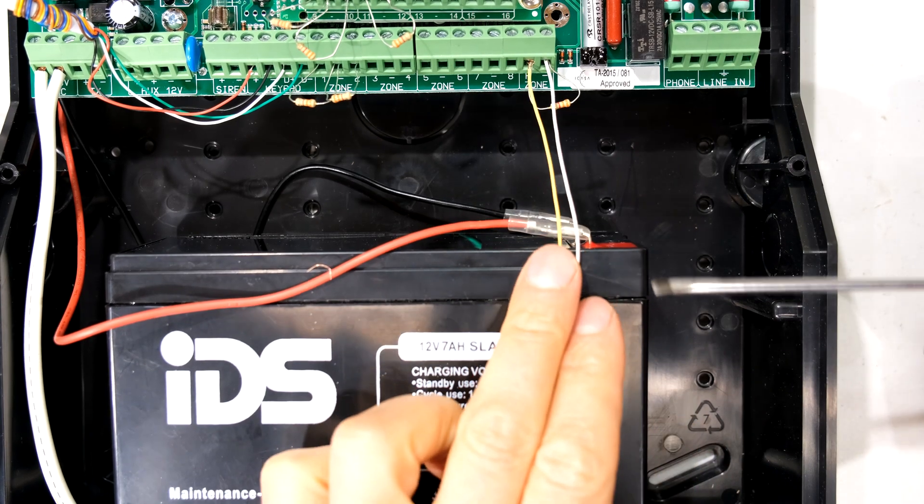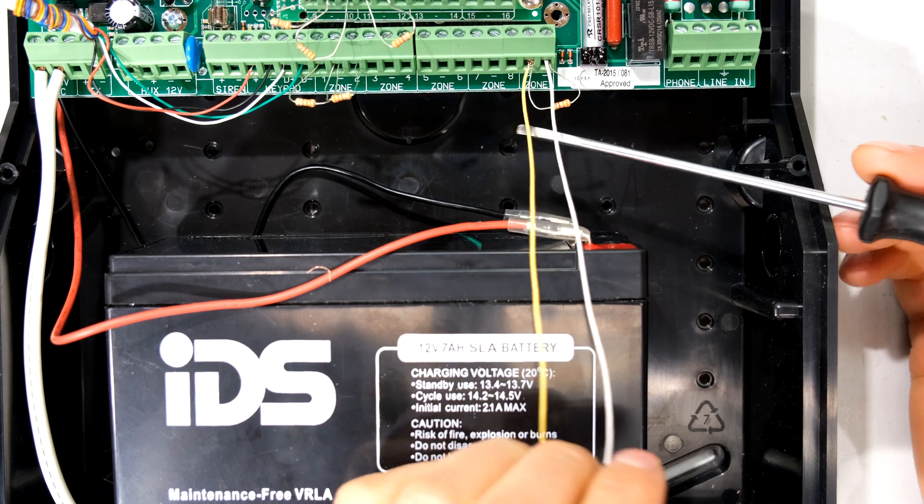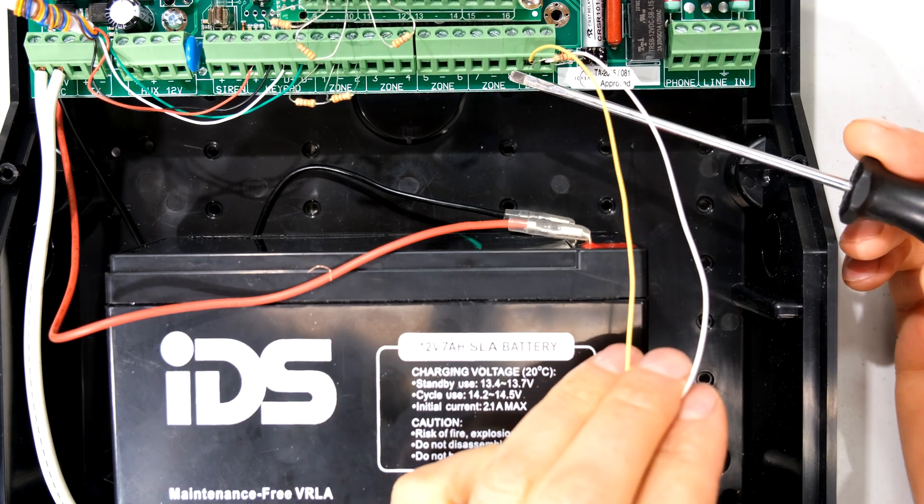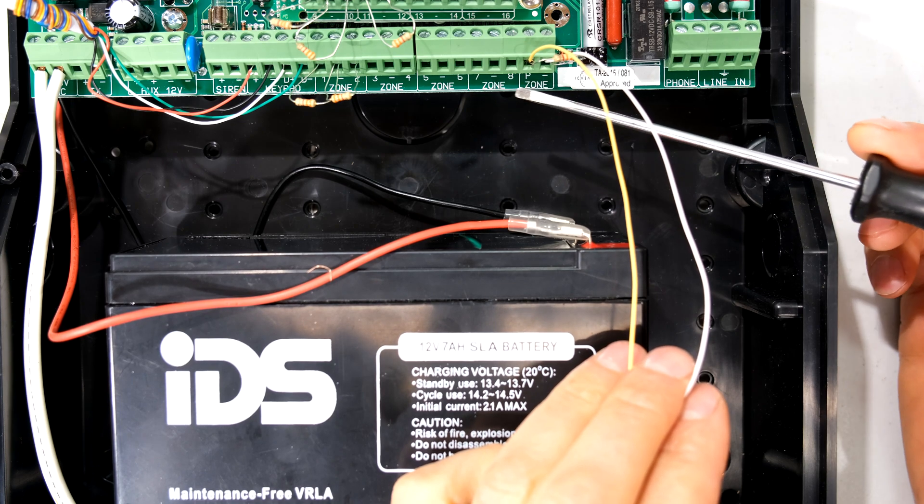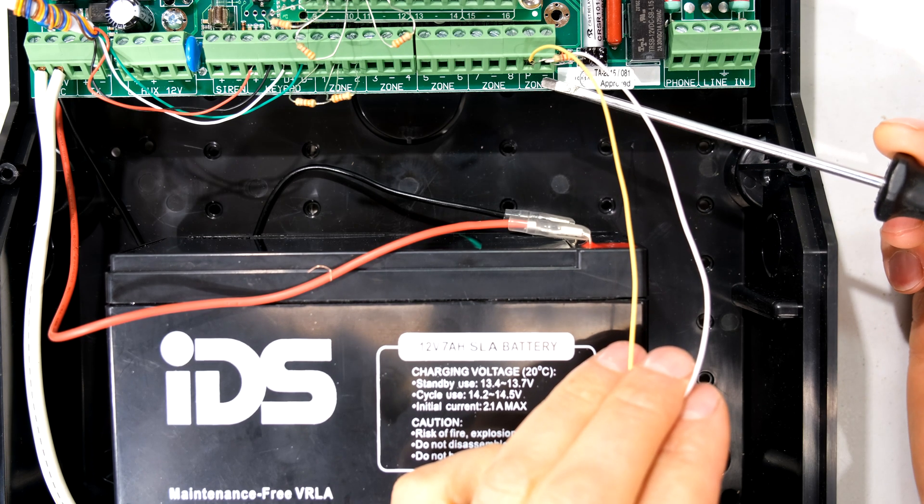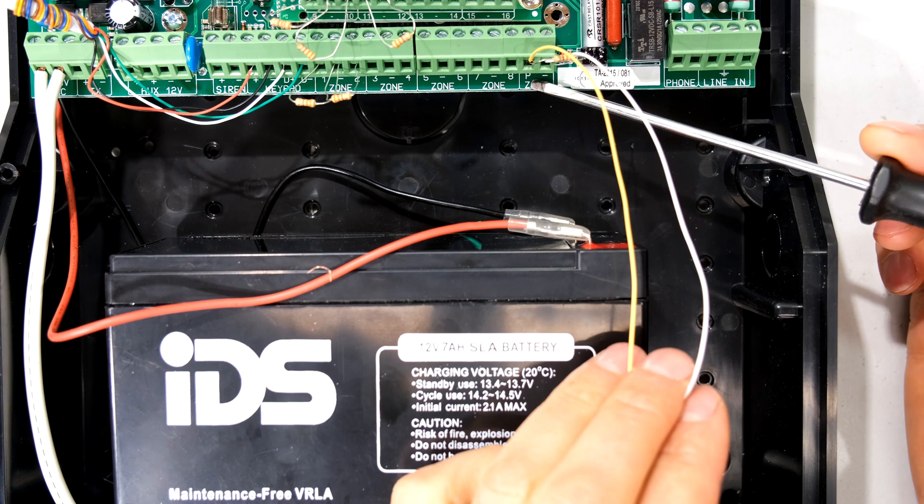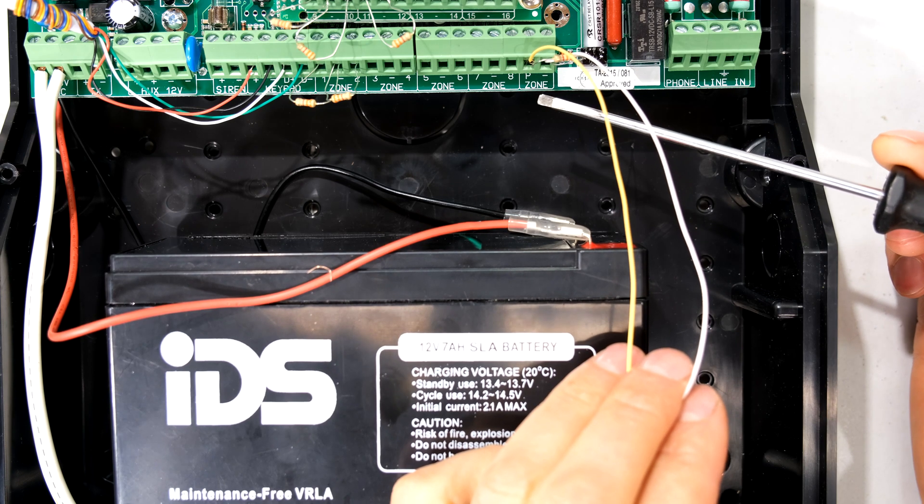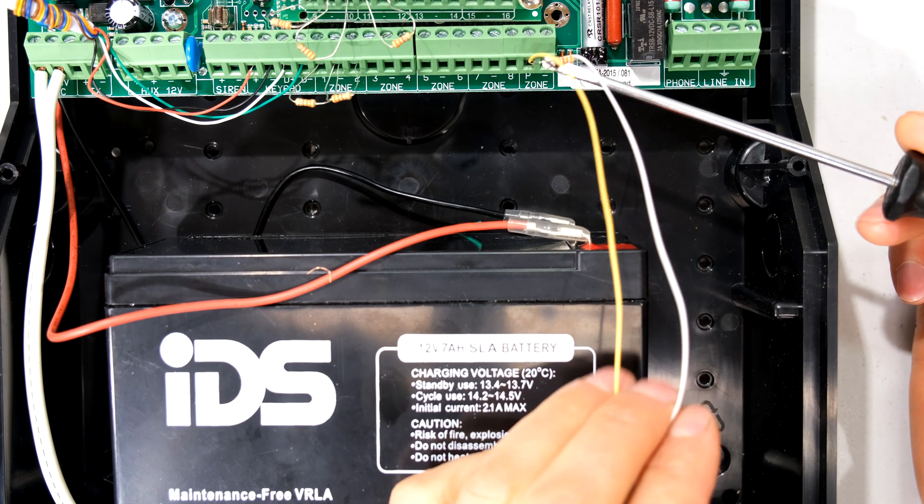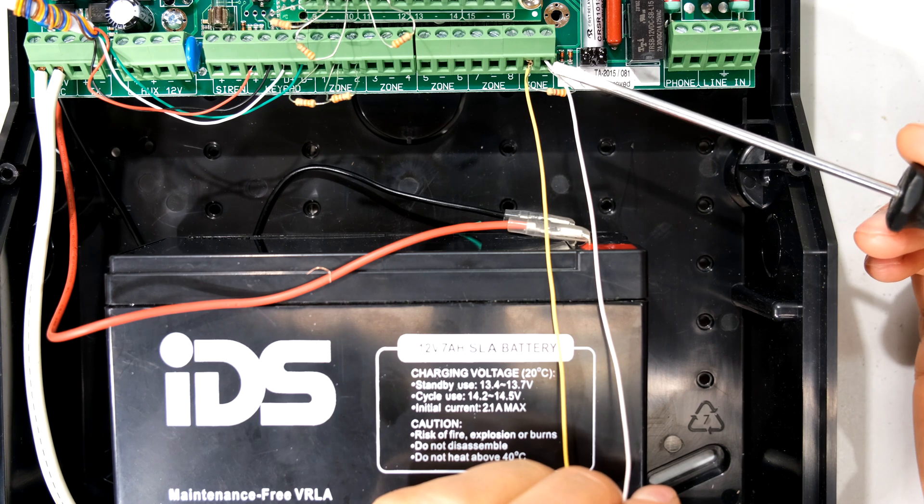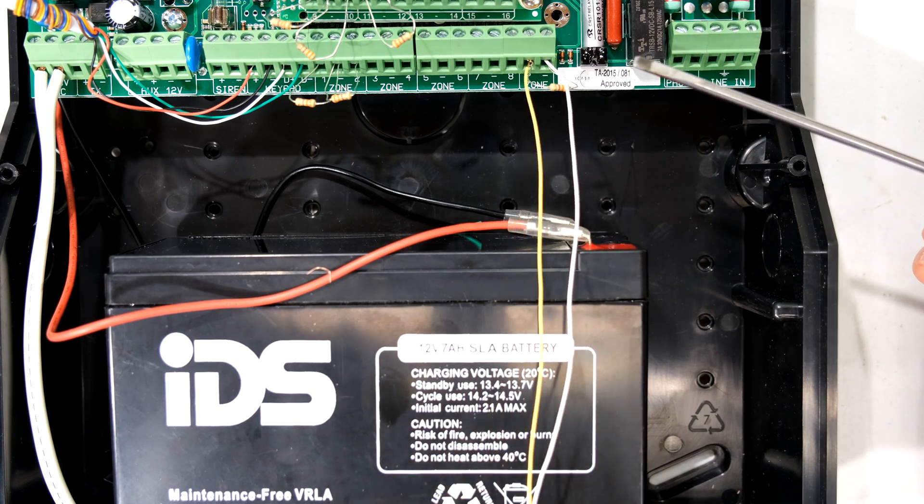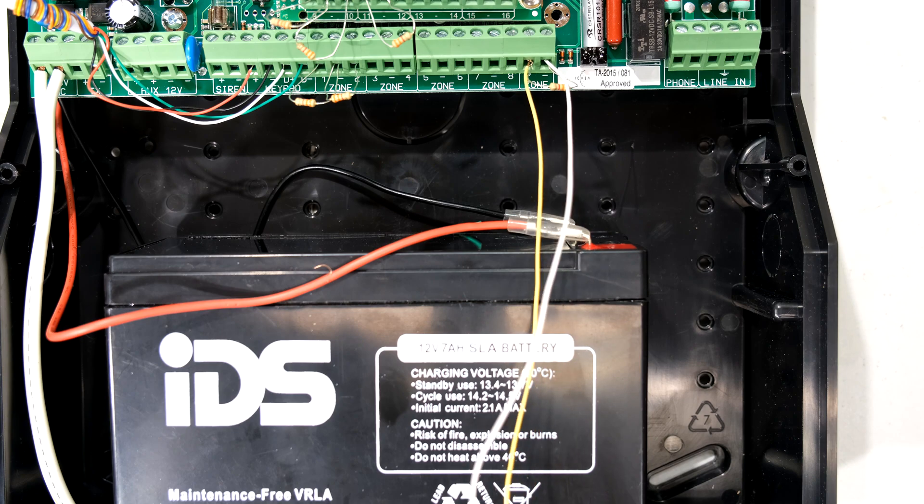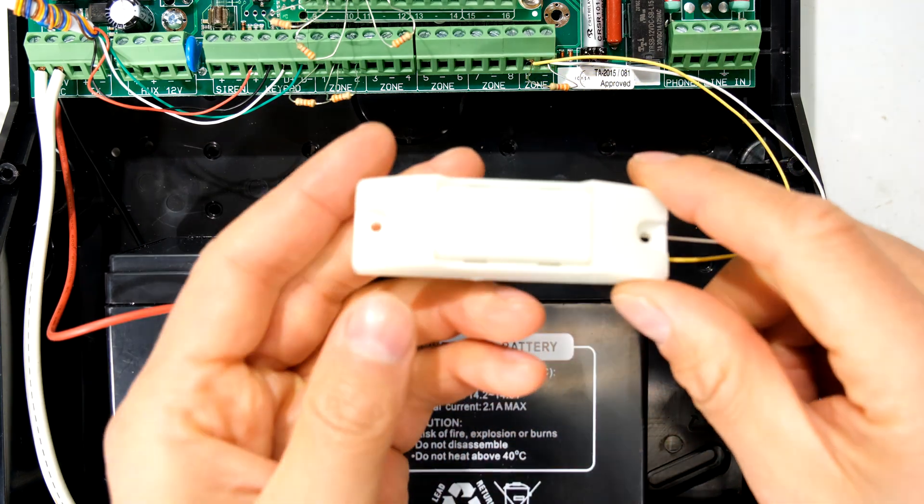Now the position for where the panic button is connected is sitting here right on the end of where the zone sits. So you can see there's zone 7, 8 and over here it says P and then minus and it says zone, P for panic zone. What you can see is I've already connected a resistor across those two terminals and there is already a panic button connected and I'm going to go through this with you step by step.